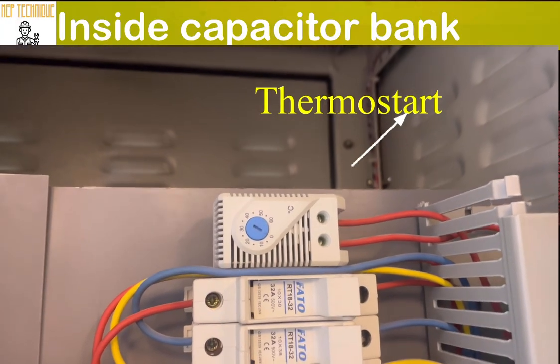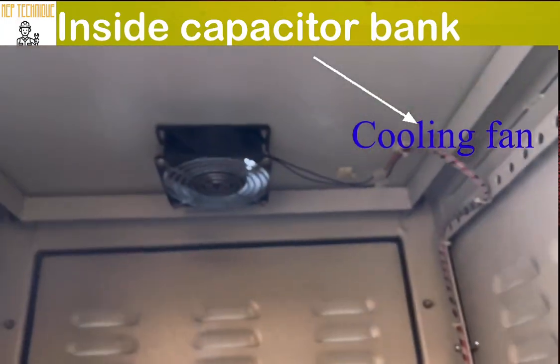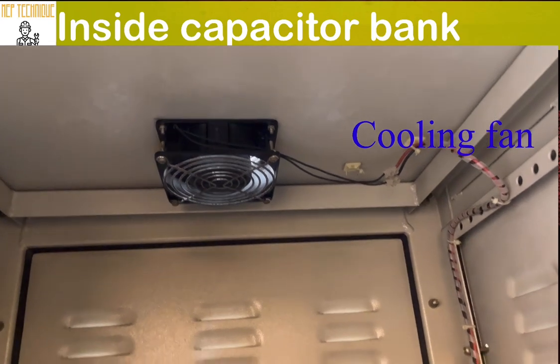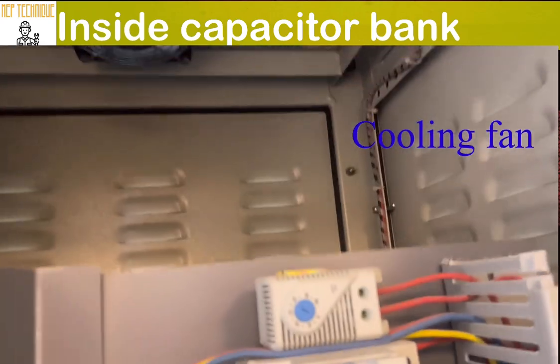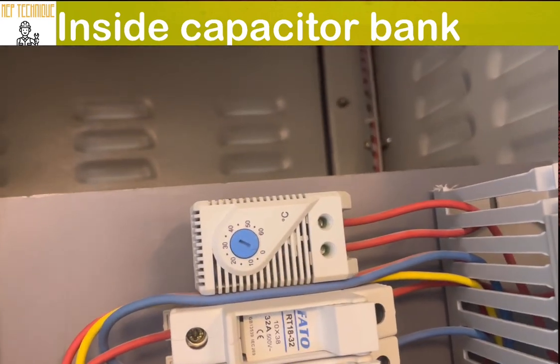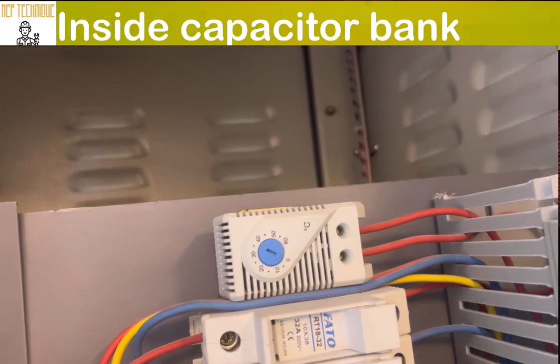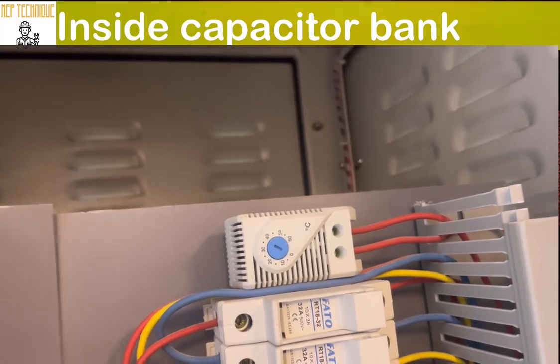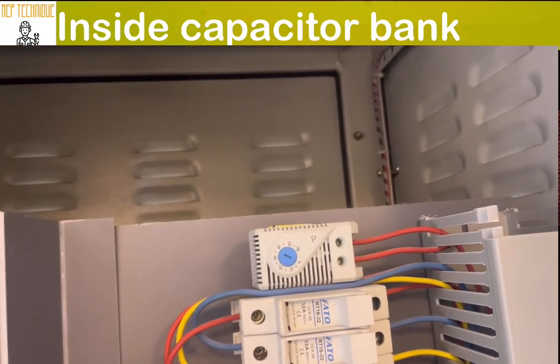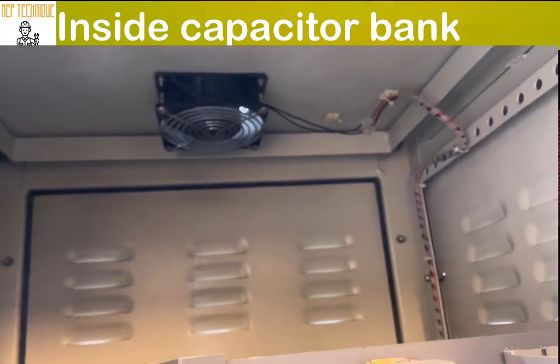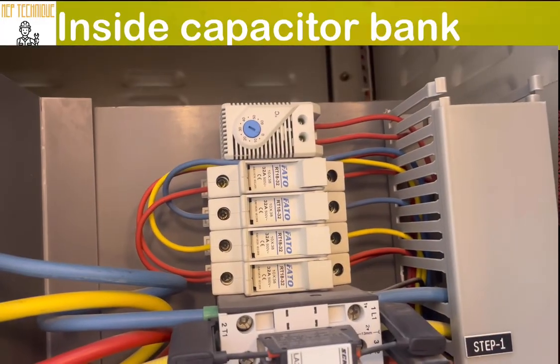The thermostat, which is controlling the cooling fan installed inside the panel, is set at 0 degrees Celsius now, but it should be set between 30 to 40 degrees Celsius. That means when the panel temperature increases beyond the limit, your cooling fan will be switched on. These are the controlling fuses.